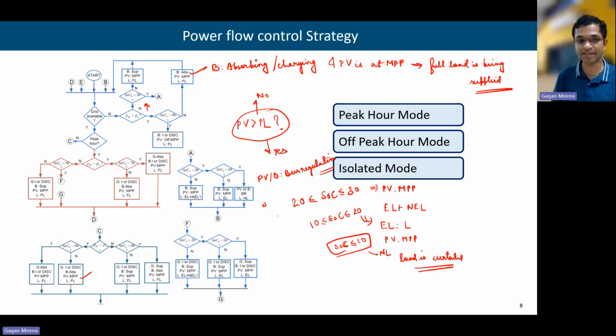Now, if the PV generation is less than the load, then we need to check SOC. If the SOC is sufficient, the battery will supply the load. Otherwise, we will take it from the grid. So let us see SOC less than 60%, or SOC more than 60%, which is this case. Then we will not take anything from the grid because this is not a peak hour. If the battery has sufficient storage, the battery can supply. PV will act as MPPT. The battery will supply, and no need to do anything with the grid. No need to take power from the grid in this case.